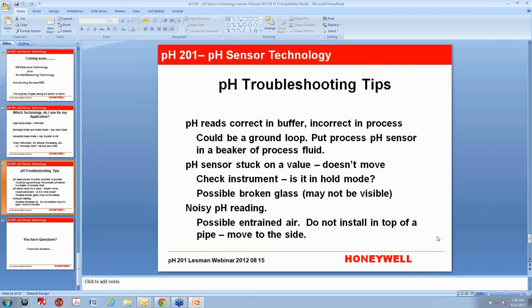A lot of people say, oh, if it sticks on 7, it's broken glass. But that's not necessarily true. I've seen them stick on all kinds of weird numbers. It doesn't really matter, because once the glass is broken, the internals start getting flooded with process fluid, and that changes all the voltage properties in the sensor. So it won't necessarily be stuck on 7. It could be stuck on anything.